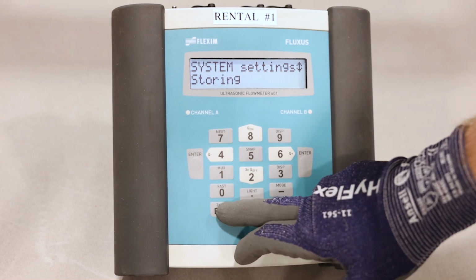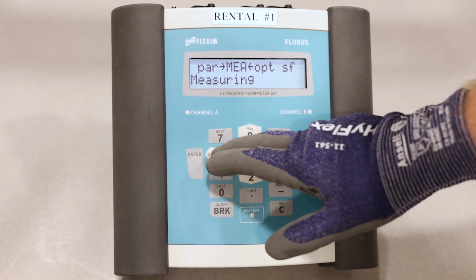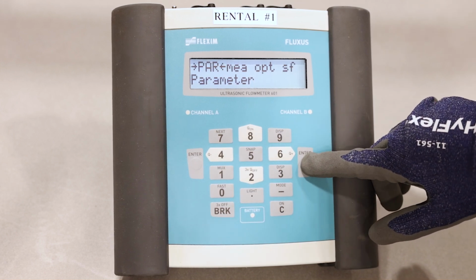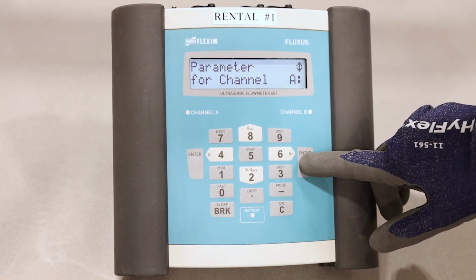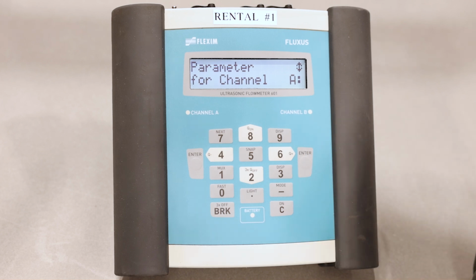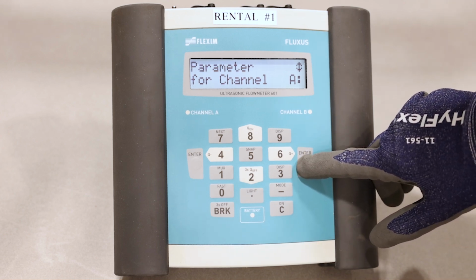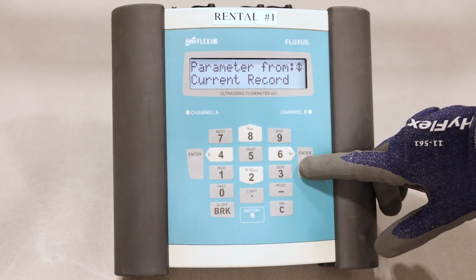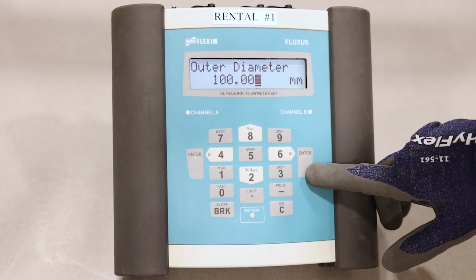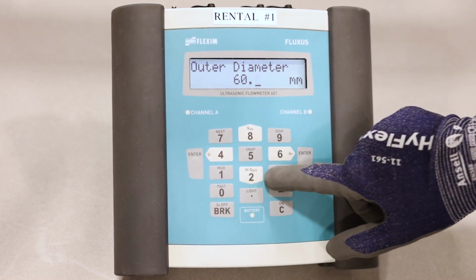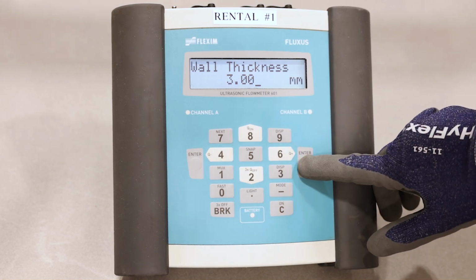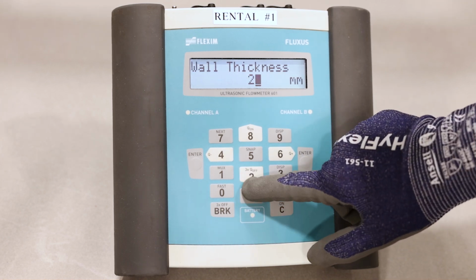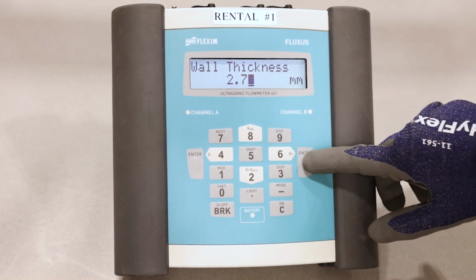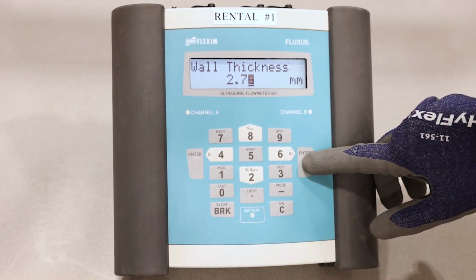In the parameters menu, we will program channel A. Prior to programming the transmitter, please refer to a spec sheet of the piping section for this information. We will be using the outer diameter for our transmitter, but you can always measure the circumference by running a measuring tape over the pipe. Enter the outer diameter of 60.33 millimeters. Enter the wall thickness of 2.76 millimeters, and we will be confirming this later with our wall thickness gauge.